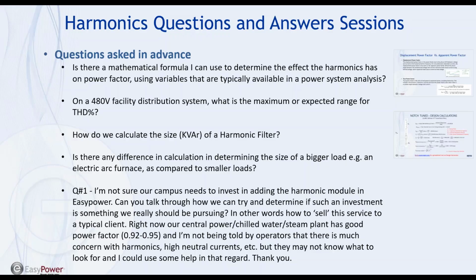All right. So next question. Okay, is there a difference in calculating or determining the size of a bigger load, for example an electric arc furnace, as compared to smaller loads? And I would say that the answer to this question is that you must be more concerned about those larger loads, the arc furnaces, the large VFD drives.